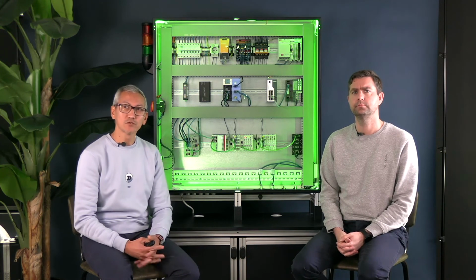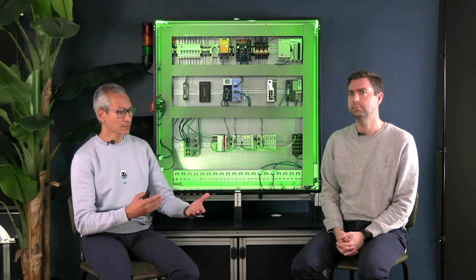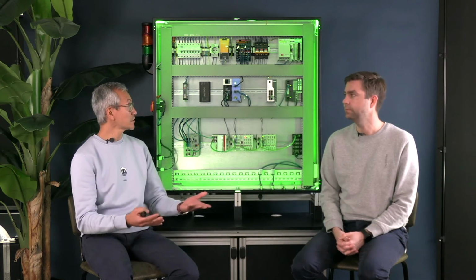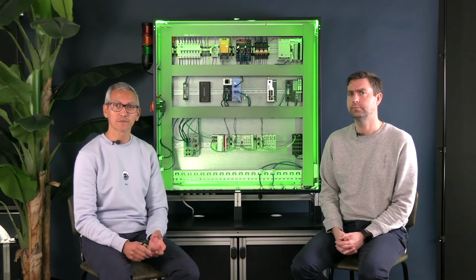So, troubleshooting made easy. We're talking about passive and active measurements. What can you do and what do you need to do? Well, if we look at our work, what we like to do is always start with active measurement because that's the easiest one. You just plug your OSIRIS on any switch. There you can already see a lot of things like duplicate addresses and device names. PROFINET works with device names, so we can also see what's happening over there.